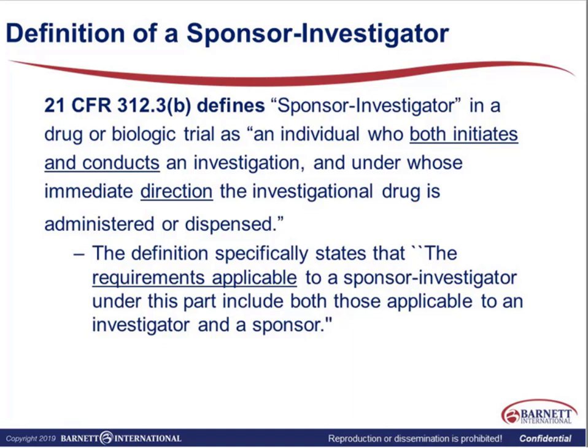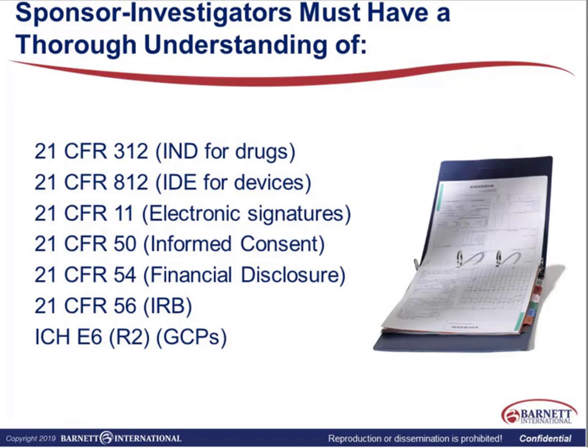The requirements of both a sponsor and an investigator need to be followed. Sponsor investigators must have a thorough understanding of the regulatory requirements for both roles. As a manufacturer, if you're providing material support — whether that be funding, biostatistics, or the investigational product — you need to understand that you are not, and cannot, take on these sponsor responsibilities, because the FDA doesn't want these types of studies used to circumvent requirements. They need to understand an IND and an IDE: what it entails, what goes into that application, what has to be structured to support that type of study.